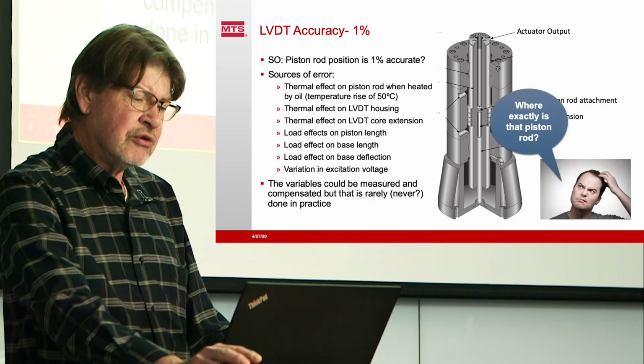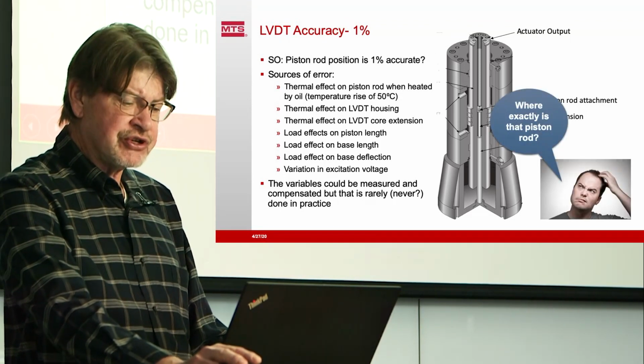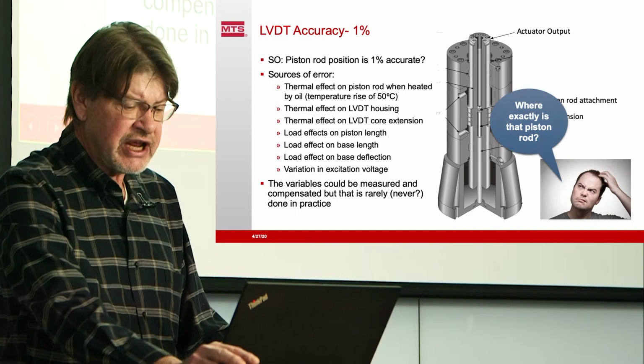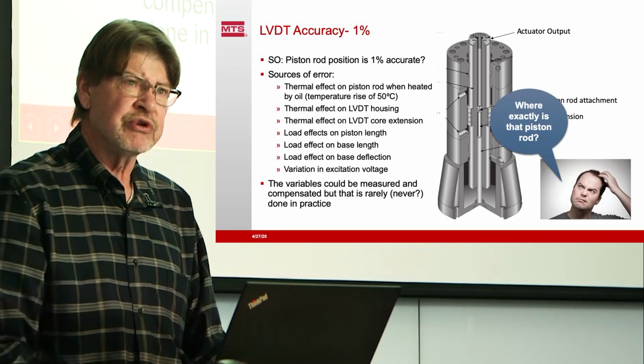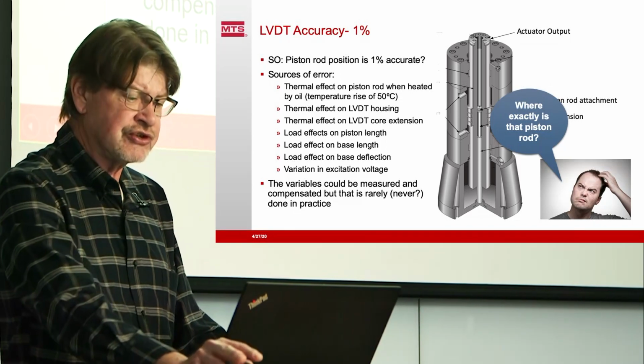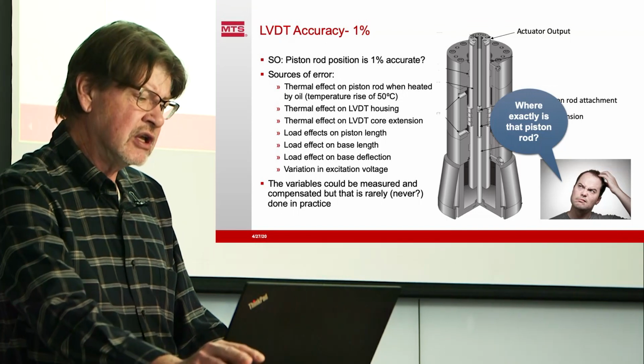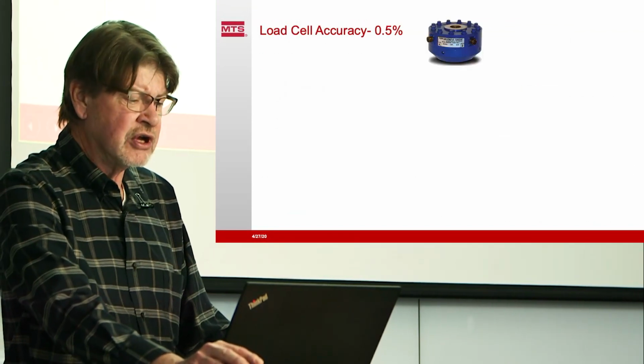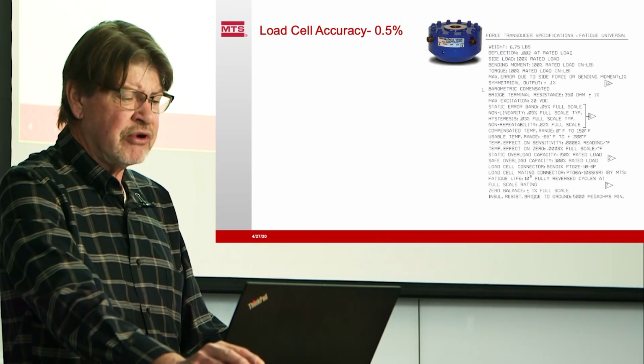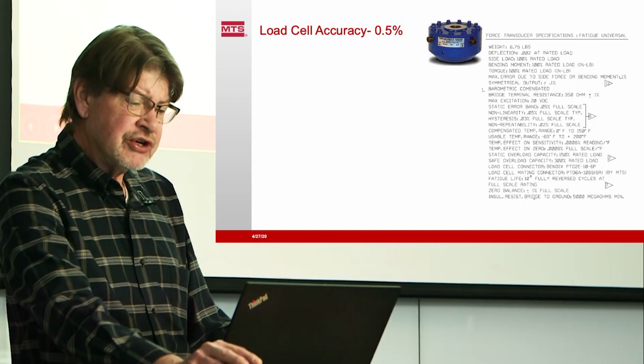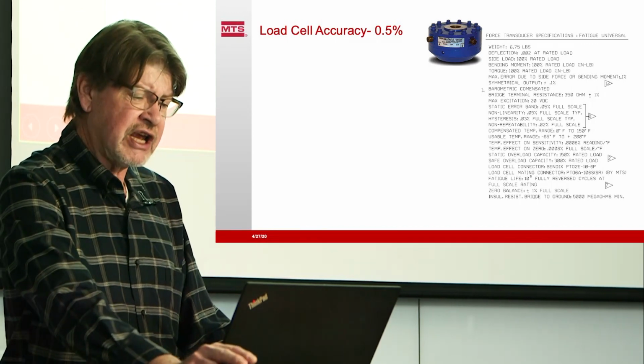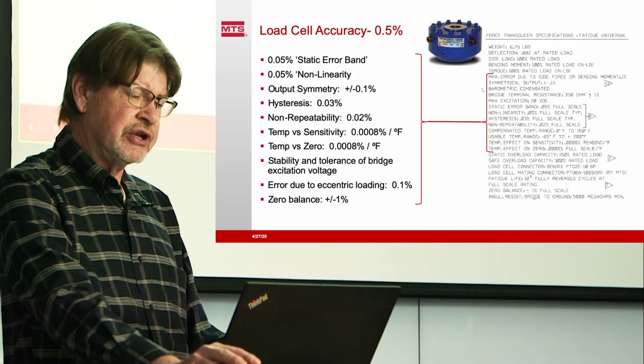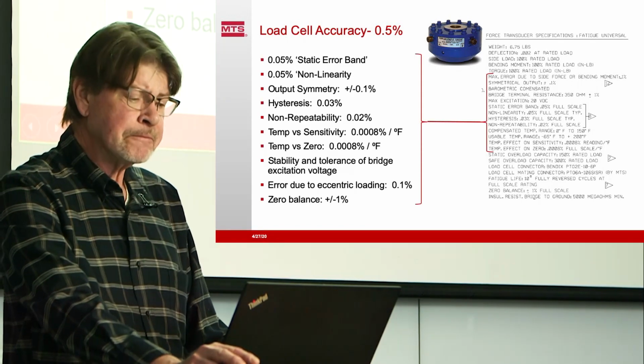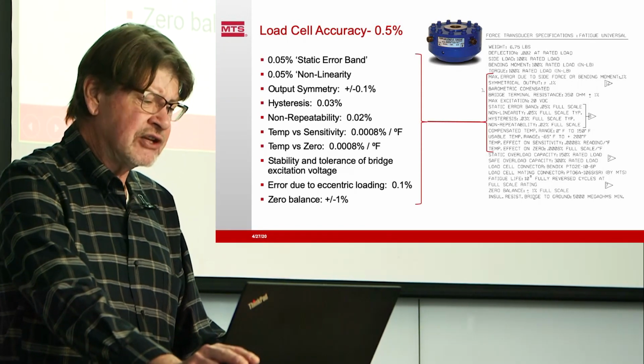But in fact, we don't know exactly where the end of the piston rod is based on the LVDT data, because we're not measuring at the point we honestly want to know. And that's just the way it works in many cases. Let's take a look at our load transducers. Load transducer accuracy, 0.5%. Well, here's the transducer specification drawing, and in the fine print, and you've got to read the fine print, we blow that up a little so you can read it.